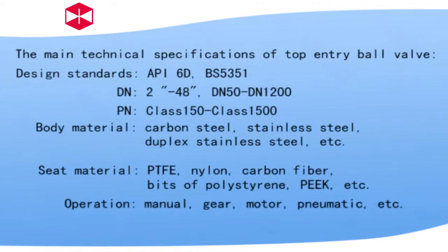The main technical specification of top entry ball valves. Design standard API 6D and BS5351. DN 2 inches to 48 inches. DN 50 to 1200. PN class 150 to class 1500.